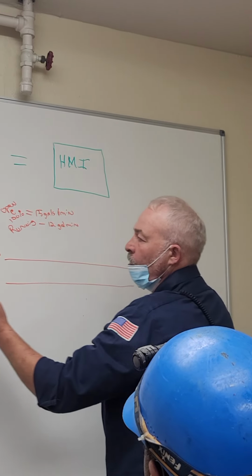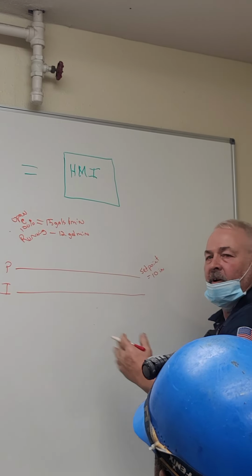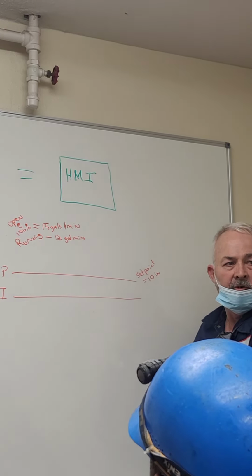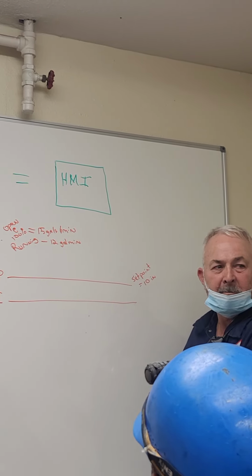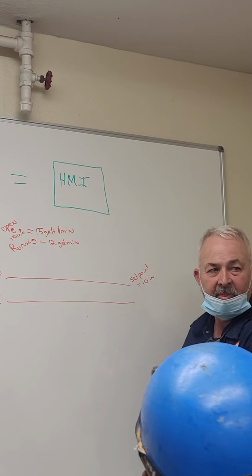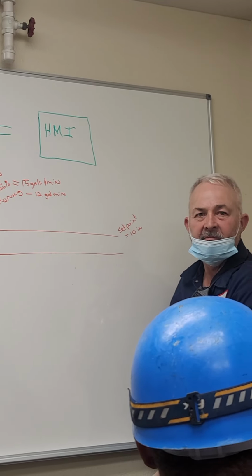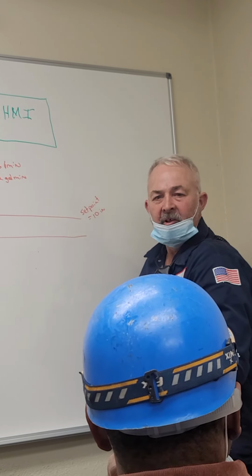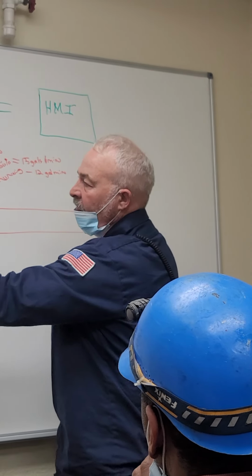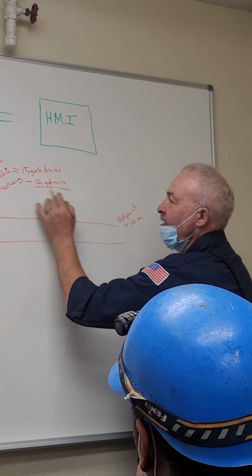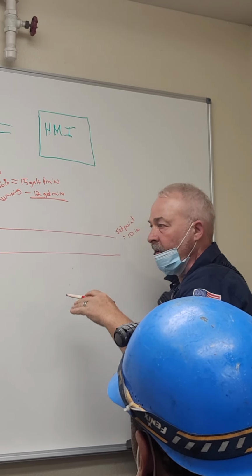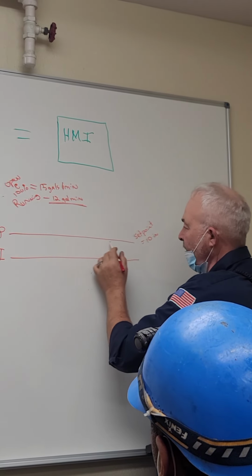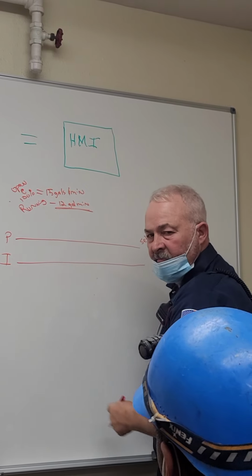You don't want to take your valve and just open and close. Why don't you want to do that? Because, like milk going into a filler, it's going to foam real bad, because you open it wide open, then it's shutting back off. So the object is to get that valve to run at 12 gallons a minute and maintain that level in that tank. So you want this line to be as straight as possible.